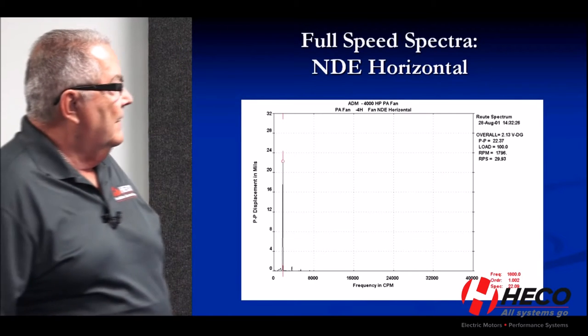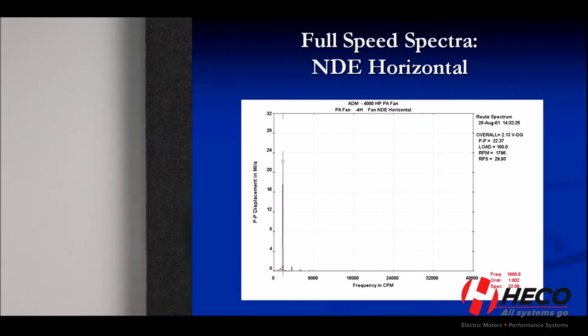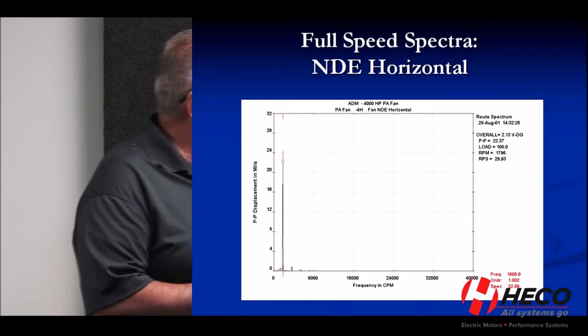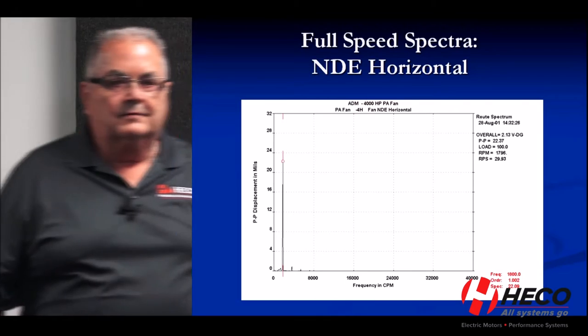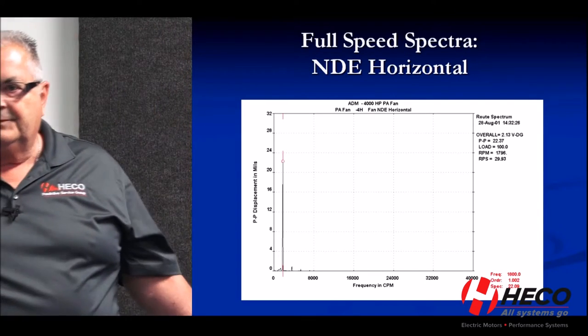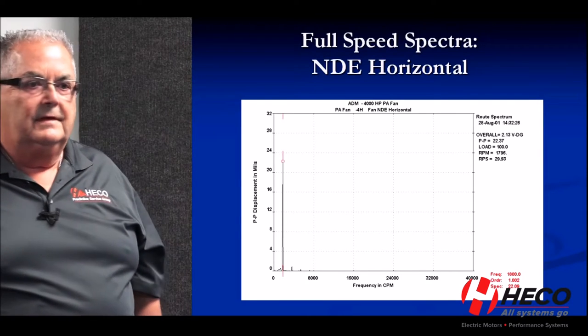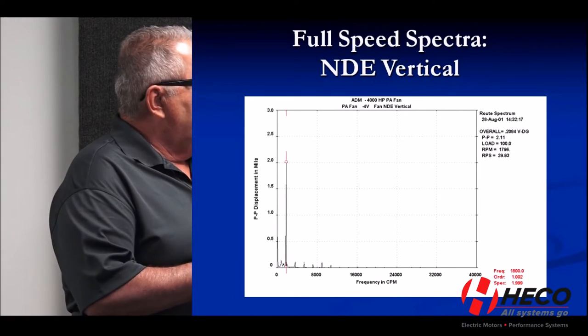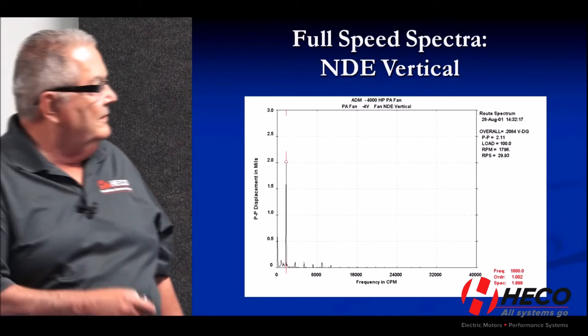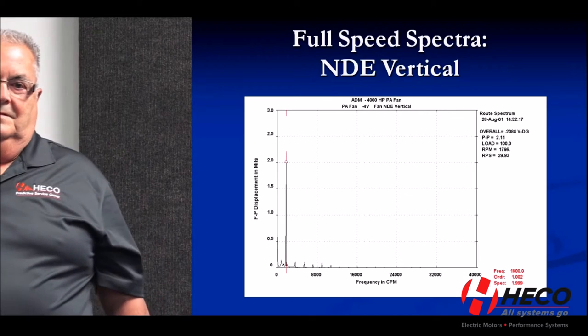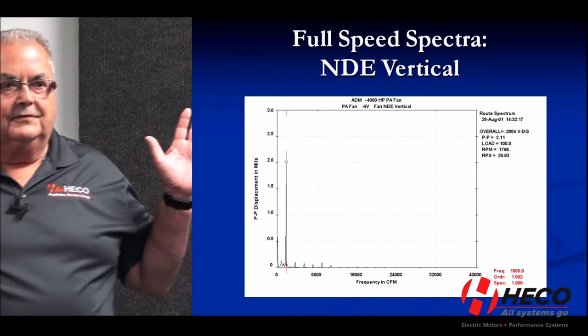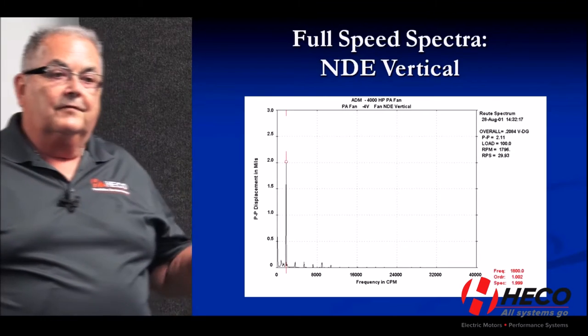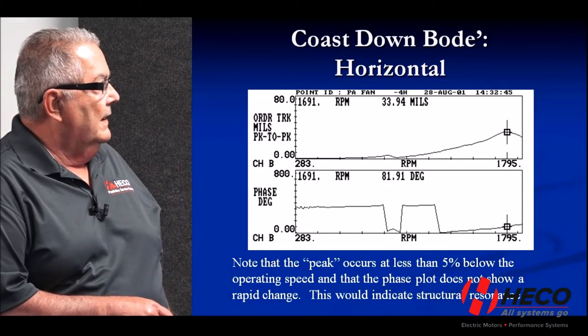We performed the initial online testing and confirmed what the tech rep had been telling us. The non-drive end horizontal showed about 22 mils at one times turning speed — a strong 1x in the horizontal. The vertical was only 2 mils, so we had a 22-to-2 ratio — an 11 to 1 ratio. Red flags go off when I see that. That says look for a resonance; it's not just a balance situation, because if it were imbalance I would expect the vertical to also be much higher than 2 mils.